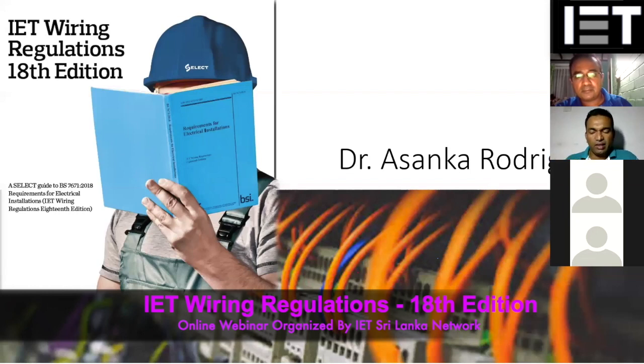So what they are telling is, you take care of your building requirement, so that if something happens, the supply system will take care of that protection. So you have to give the protection for your building, and you have to have the coordination there, so that if a live wire connects to the metal pipeline within your building, that will be taken care of if you connect them to an equipotential bonding.